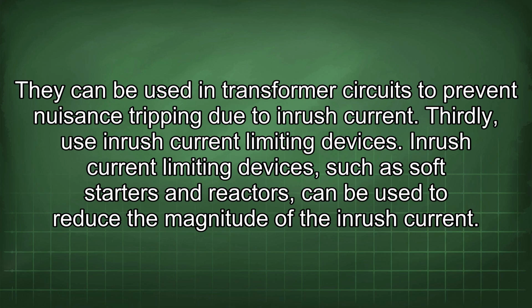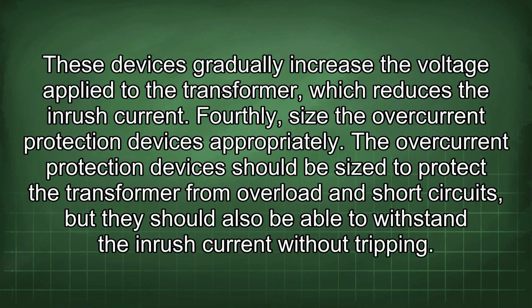Thirdly, use inrush current limiting devices. Inrush current limiting devices such as soft starters and reactors can be used to reduce the magnitude of the inrush current. These devices gradually increase the voltage applied to the transformer, which reduces the inrush current.